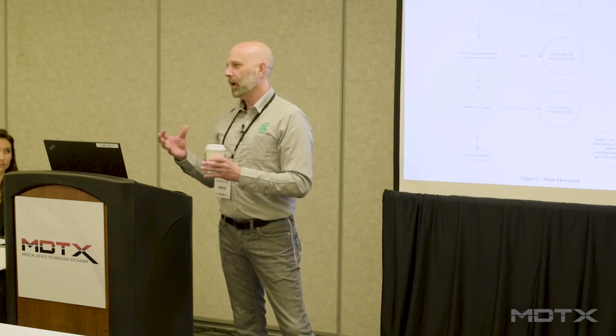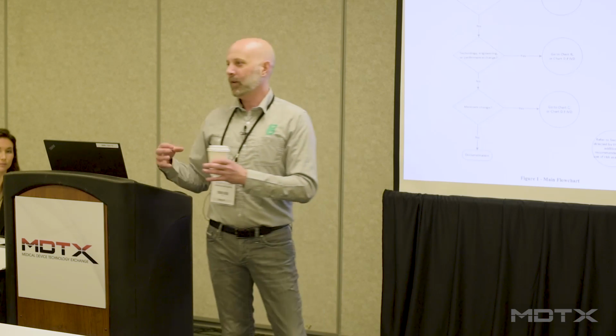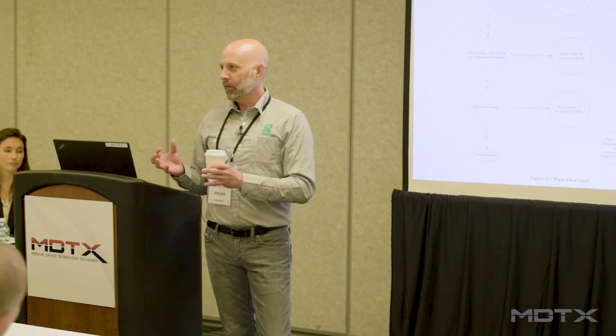Really, really good points. And you want to talk about design change? Sometimes I think people hear that term and they think, oh, that's just a design control change that I focus on during the product development process. Not exactly. If I make a change even after I do design transfer, that is potentially a design change. Right? So design control is a total product lifecycle process. So if I make one change to a product, I have to understand the design control ramifications, the risk ramifications, the regulatory ramifications, and I should keep my design control traceability matrix fluid and up to date and current with my product as it evolves and changes.